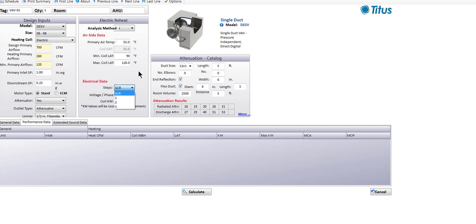The ultimate control for an electric coil these days is an SCR coil. SCR stands for Silicon Controlled Rectifier, and these heaters had a bad name for a long time because they used to be very expensive and unreliable back in the 1980s and 1990s. Today, SCR has become a generic term for a modulating electric coil. When you look inside today's SCR heater, you won't find an SCR — you'll find a digital control board that fires low voltage solid state relays rather than using old SCR technology.